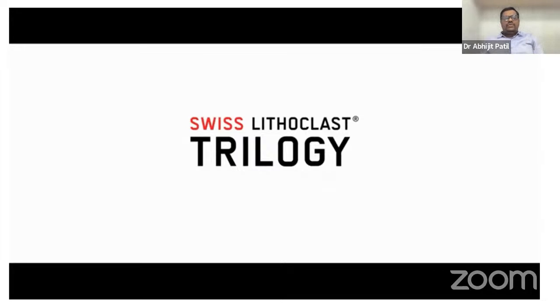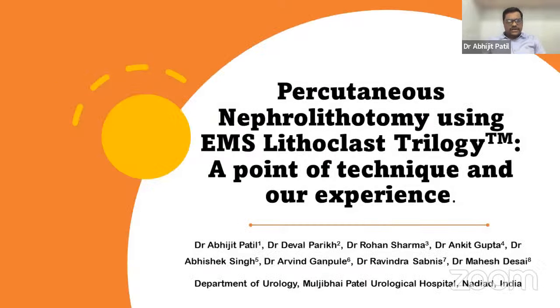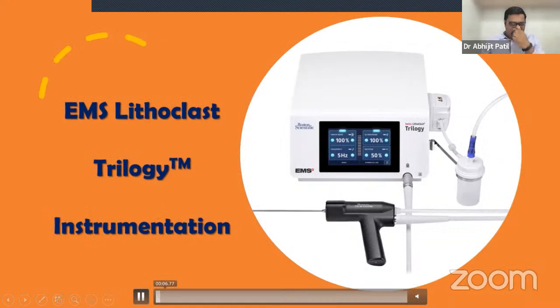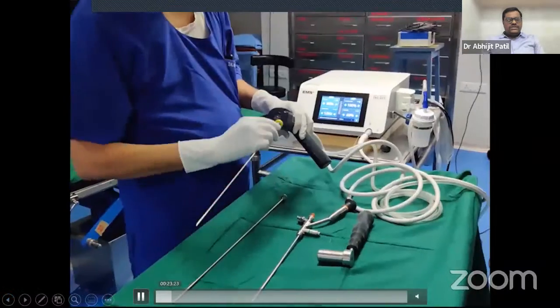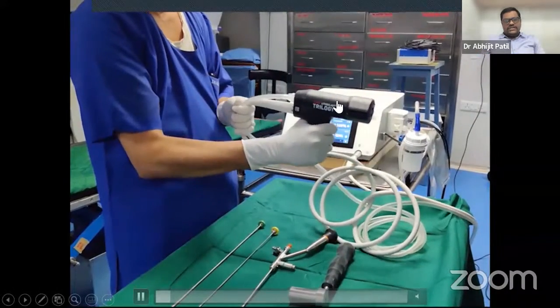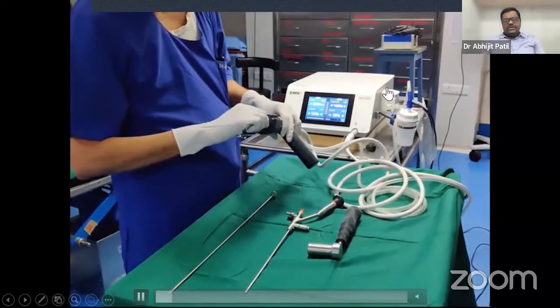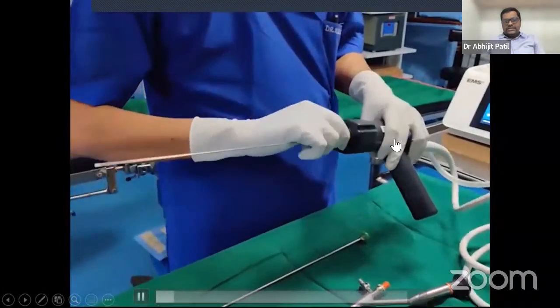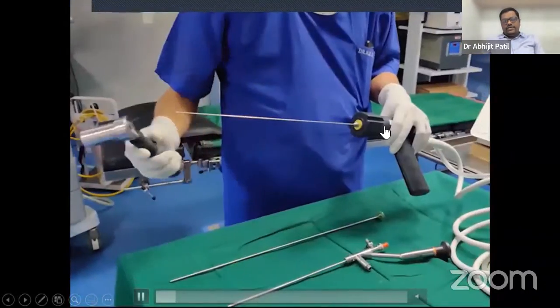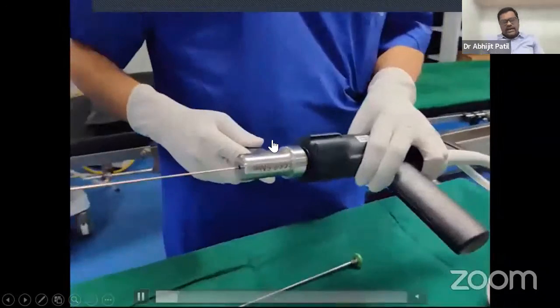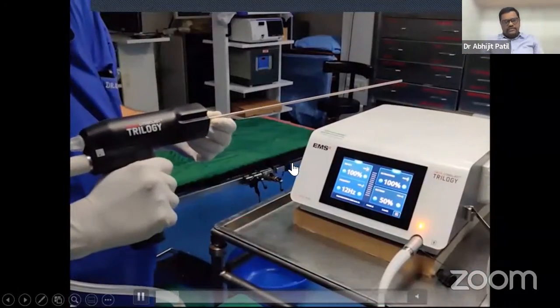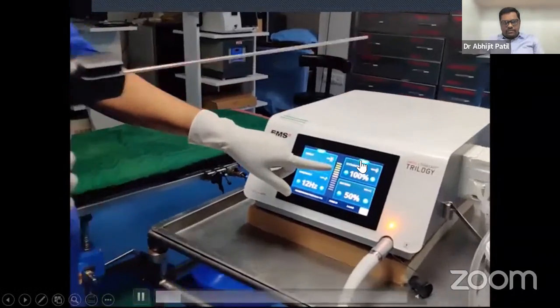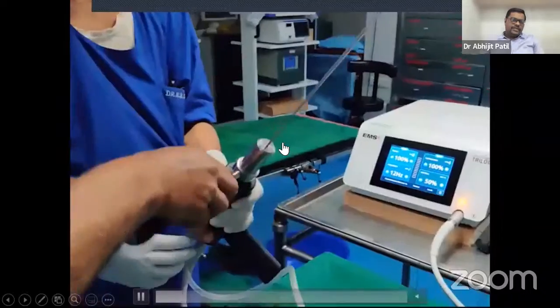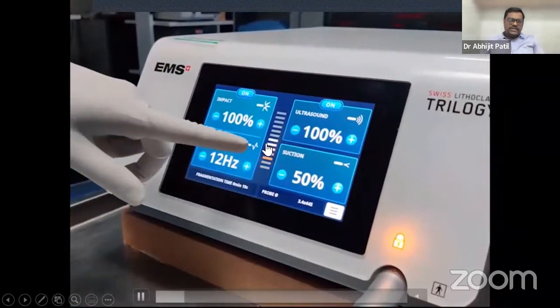Now presenting our own experience of Lithoclast Trilogy. So first I would like to show the instrumentation of a Lithoclast Trilogy. So this is the setup of a Trilogy, where this is the handpiece, this is the cable where you attach to the machine, and this is the suction tubing. This is the probe where you attach using a clockwise manner, and this is a torque wrench where you tighten it. Now if it is tightened properly, you will get a green color feedback. Now, if it is malfunctioning, you can see it turns orange.